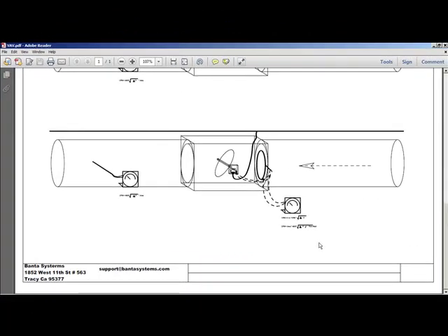Okay, say we run into a VAV box and we don't know who the manufacturer is and we don't know what the K factor is. The first thing we're going to want to do is disconnect the controller, press the release button and adjust the damper so that we're midway. We want to take control of the fan, increase or decrease the fan airflow so that we achieve 1 inch, and then we'll lock the fan down, and then measure the output of the box at that 1 inch pressure drop.